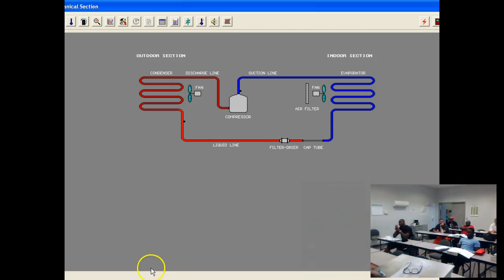Down here, depending on how complicated this is, you may have more than one circuit breaker, but on the air conditioners, we only have one circuit breaker. Click on. Now, y'all might be able to see on the projector, I've got the fan blade running for both the condenser and the fan. Can y'all see that from back there? Yeah. On the little screens, it's a lot easier. And that's a dead giveaway. If you walked up to a condenser and you heard it humming, but the blade's not running, you're probably going to go, I think it may be the fan, or the capacitor, or the wiring to it. All right, and on the little computers, we can actually see bubbles flowing through this, little white lights. So you can also see if the compressor's running.